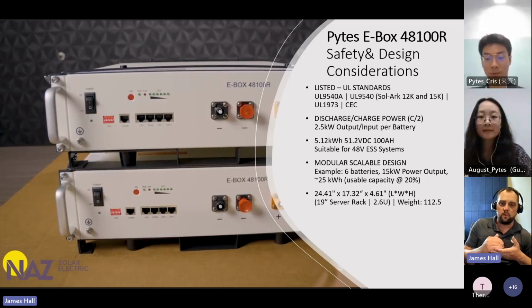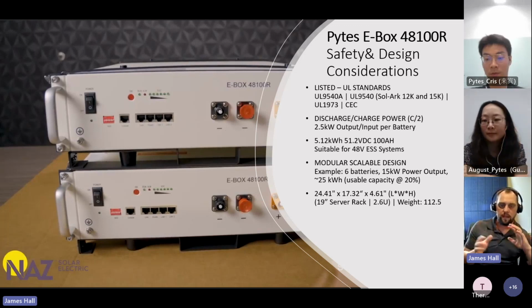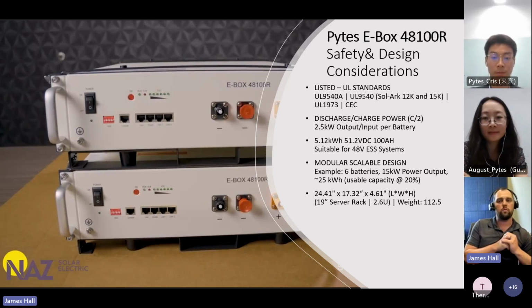But UL 9540A is becoming even more important - that's a fire propagation test, showing that the battery is not going to catch fire and propagate, causing a matchstick situation. That's really important with lithium batteries because everyone's concerned with fire safety. Having these listings, 9540, 9540A, and 1973, is super important in our designs, and that's why we chose to go with Pytes for this type of battery.